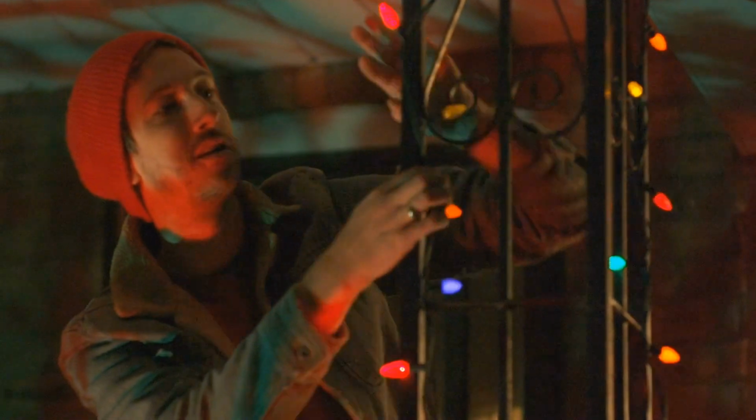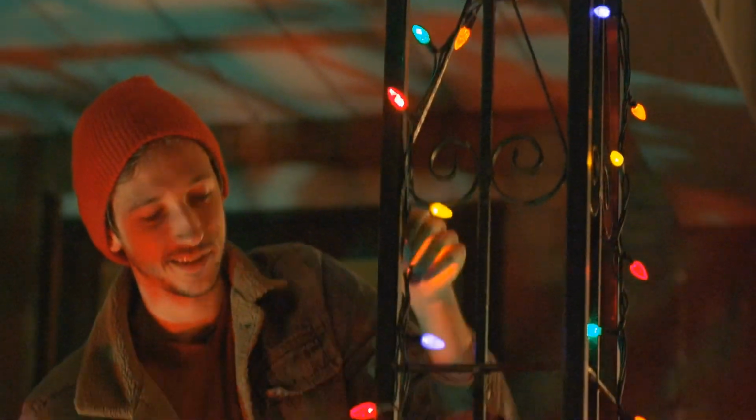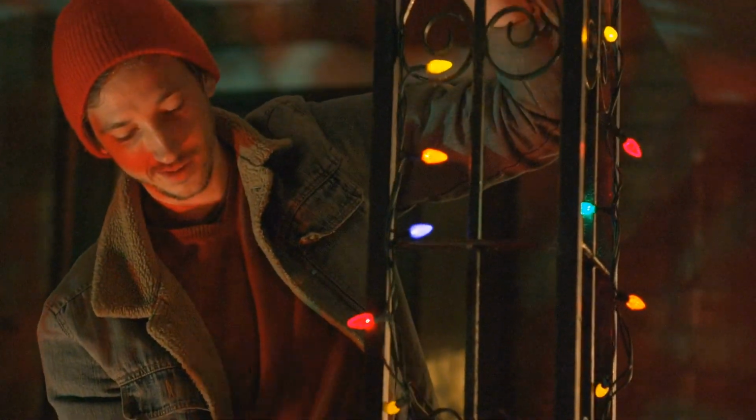If you come out and it pops right back, that's because water has gotten into one of the connections, and a lot of times this is due to minis, especially if you get cheap minis. I know some of you are like, let's go to this local place that sells you crappy minis, and this will be a problem for you a lot of times.